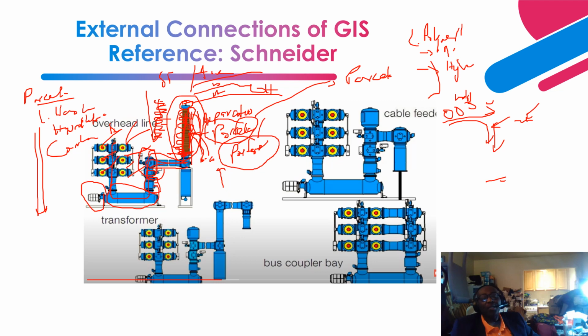Another external connection that you can have is a cable feeder, right? Coming from here. If you have a 220 kV, 380 kV feeder cable that comes in here, right? That is connected to this SF6 chamber, right? Then from here, it is all filled with SF6, right? All filled with SF6, right? So this one is air on this side, then SF6. So this is an air to SF6 interface or interchange, right?